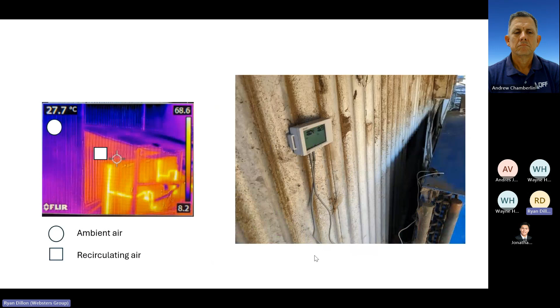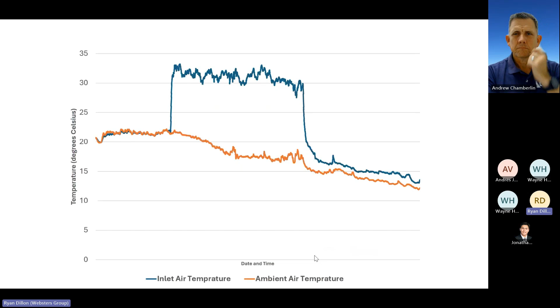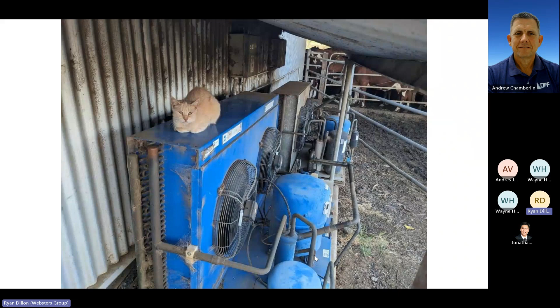So in farmer language, or in layman's terms, it's sucking in its own juice, it's rejecting this air, and it's similar to running the system in winter as if it was summer. Now, while we're going quite technical here, another indication might be the fact that on a really cold winter's day, the cat's hanging out up there, and it's really warm, like you can physically feel it. And this air is basically just hitting this roof, recirculating back into the condenser. Nice, cozy environment, but not good for the energy bill. So thermal imaging helps identify these problem areas with further analysis with temperature data loggers.